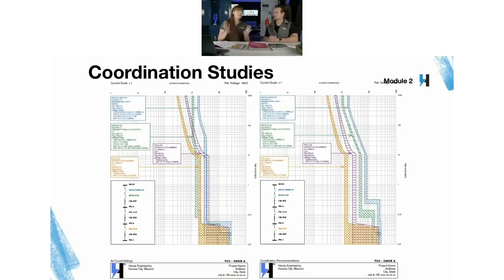Mind you, again, huge disclaimer, there's a lot more to it than that, but that's kind of the 1,000-foot view. For instance, the curve in blue is 1600 amps, so that would fall under the 240.87 rule for any device over 1200 amps. Yep. Unfortunately, we didn't show the arcing fault current line on this, but if you want, I can send that to you later and we can talk more about it. There we go.